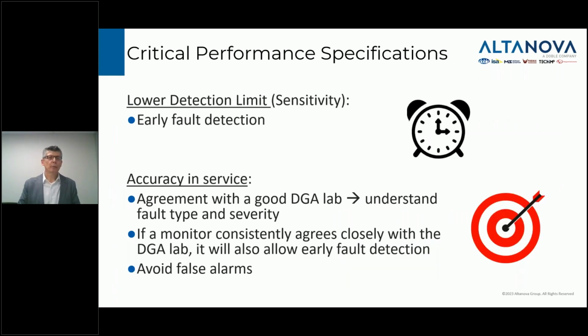When I think of the critical performance specifications for DGA monitors in general, sensitivity is important for early fault detection. The other parameter that's really essential is what we call accuracy in service. What I mean by that is, if you look at the readings coming out of the DGA monitor, how well do they compare with a good DGA lab? The advantage of a monitor that's accurate enough to agree with the lab is that at any point in the year, you can understand if there's a fault, and more than that, what kind of fault it is. And if it's a severe fault, you can actually classify the fault if you've got good enough accuracy from your monitor.